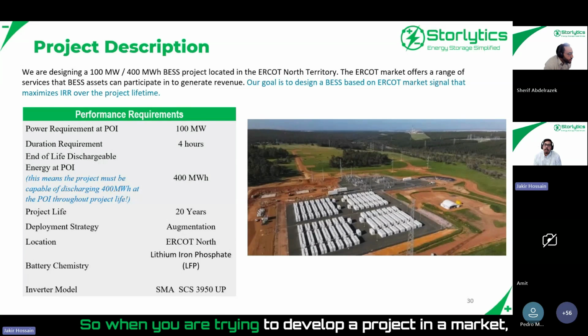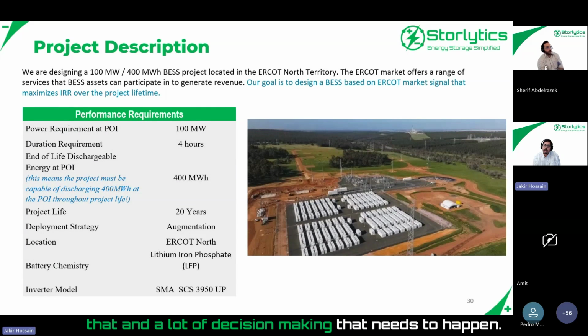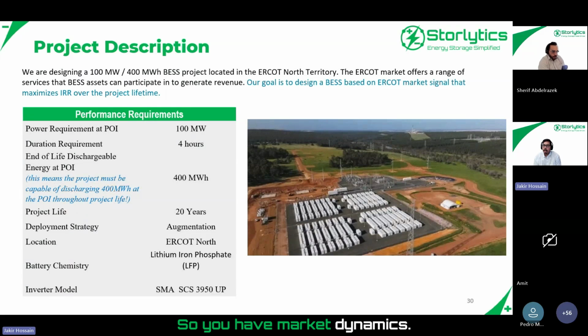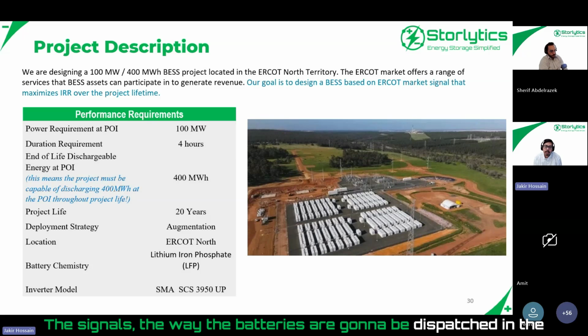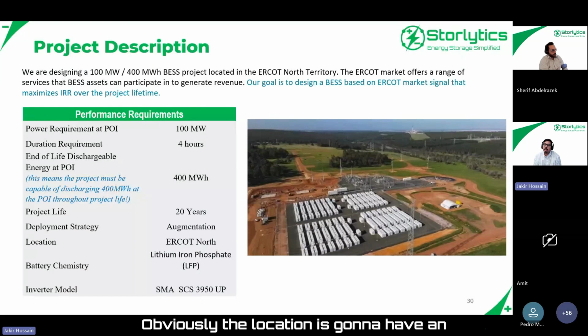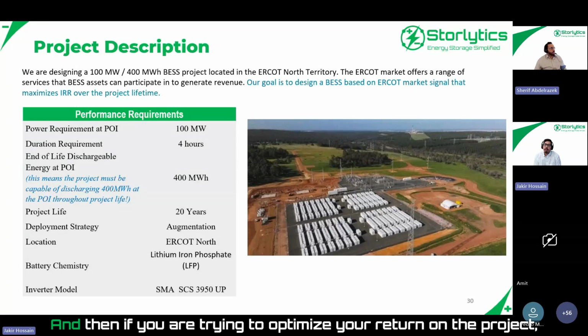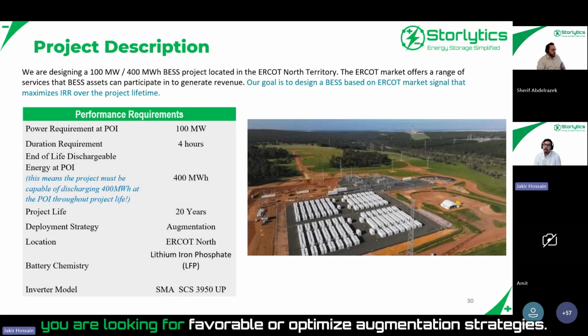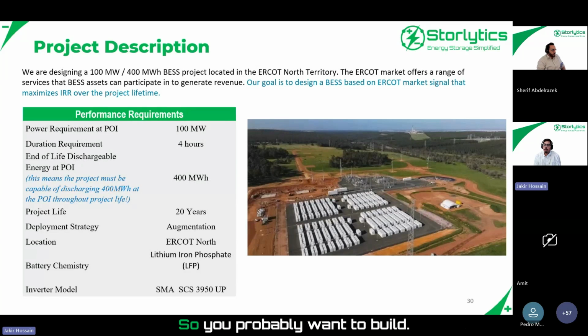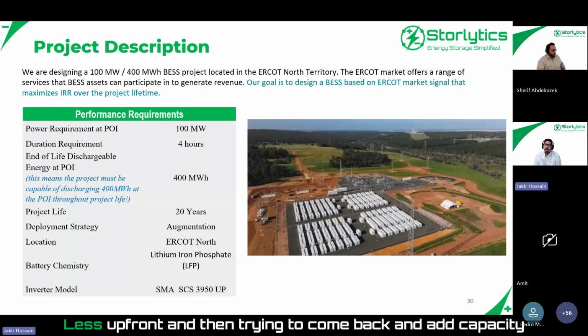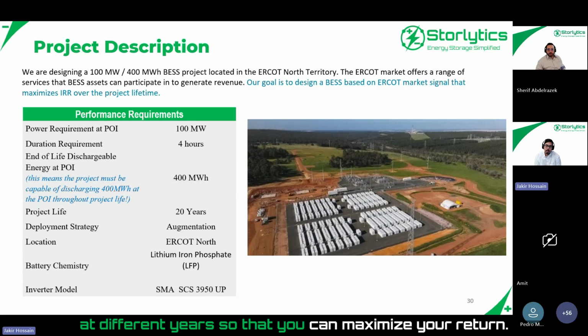So when you are trying to develop a project in a market, there are a lot of different variables associated with that and a lot of decision making that needs to happen. So you have market dynamics, the signals, the way the batteries are going to be dispatched in the market is going to vary from market to market and market rules. Obviously, the location is going to have an impact on your auxiliary consumptions. And then if you are trying to optimize your return on the project, you are looking for favorable or optimized augmentation strategies. So you probably want to build less upfront and then come back and add capacity at different years so that you can maximize your return.